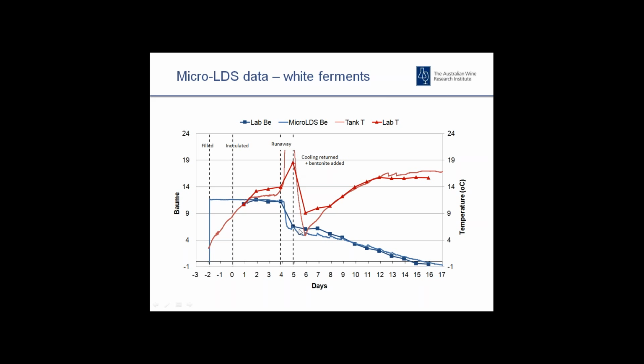So if you look from day 5 onwards, you can see that sensor tracked the reference Baume relatively closely, probably as well as any of the 3 sensors did. We did, however, experience some issues with the sampling cycle that we're using. We automatically sampled every 2 hours, but the volume that was sampled in the early stages was not high enough to flush out the sample loop. So we increased that volume from about day 7, day 8 in order to make sure that we had a fresh sample going through the sensor at each sampling point.